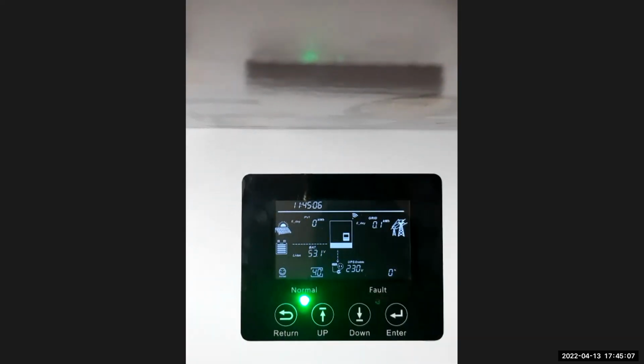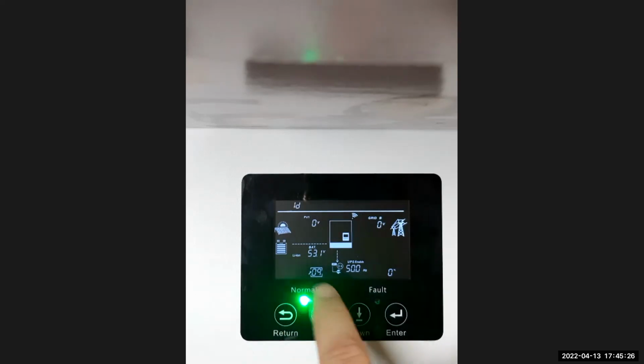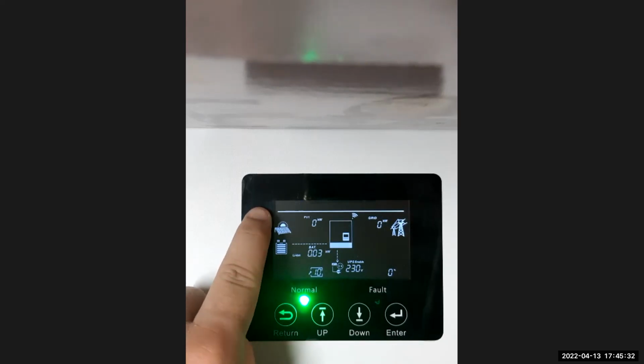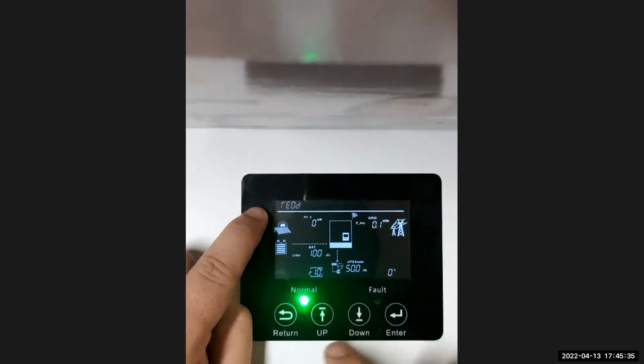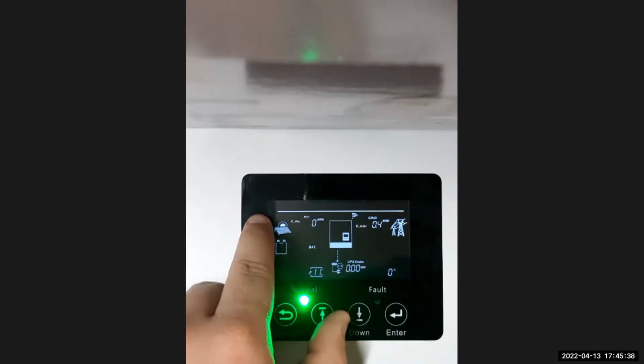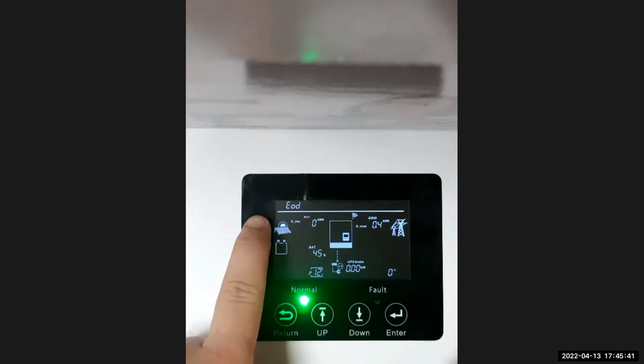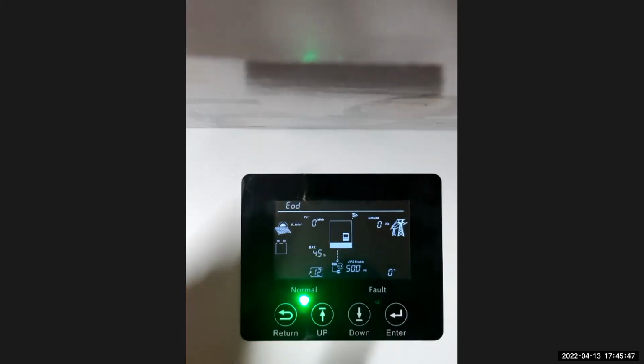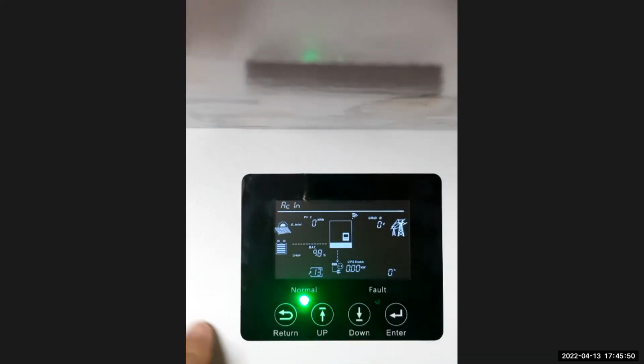So just to recap on this machine, there are a few settings that you'll always play with or change. First of them will be number 3. That's your battery settings. Number 6, your charging settings. 7 and 8 are your float and your charge settings for when it's set to lead acid. Number 9 is to tell your inverter what to use, voltage or SOC, for the parameters that you're putting in. Number 11 is your cutoff voltage. That's where your inverter stops working. Number 12 is for when it jumps back from the batteries to the grid, when grid is available, that percentage that you use there. Then AC in.